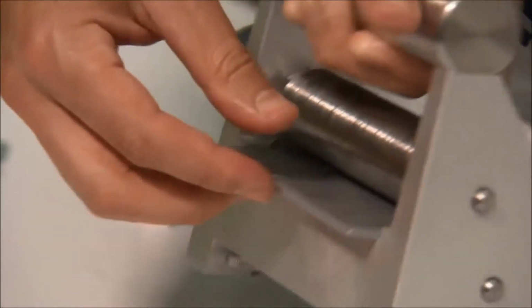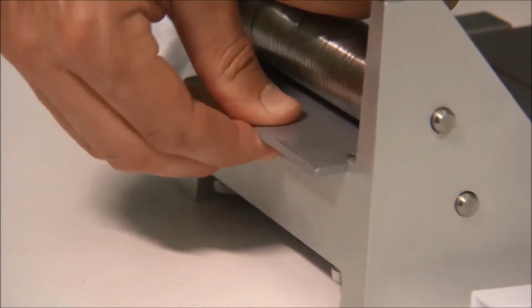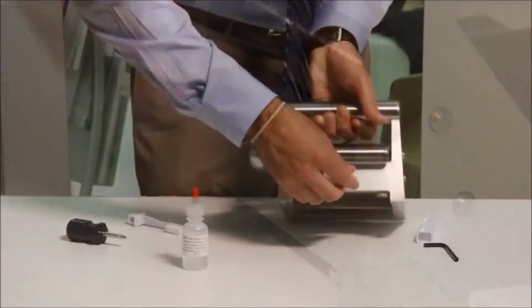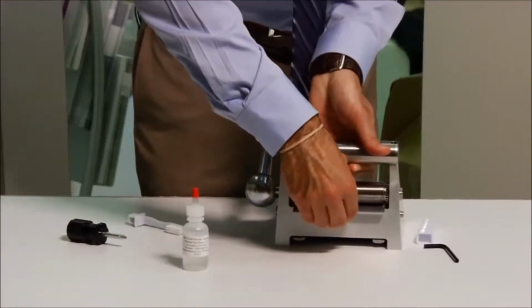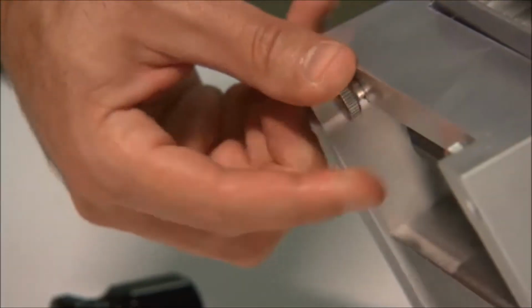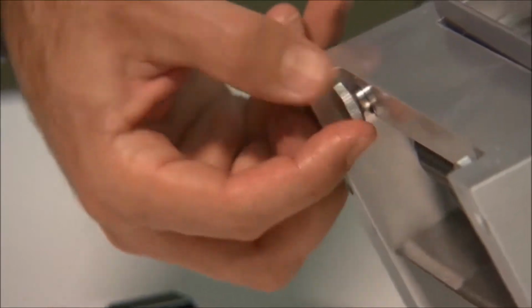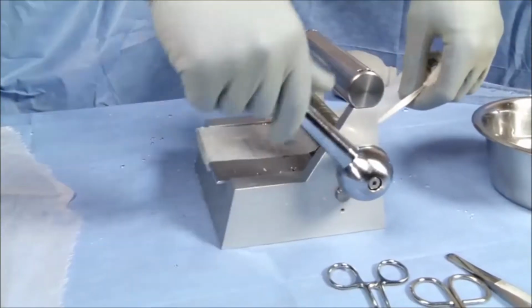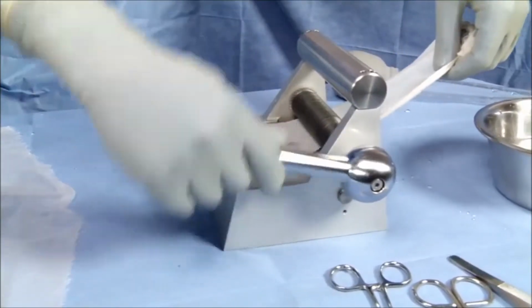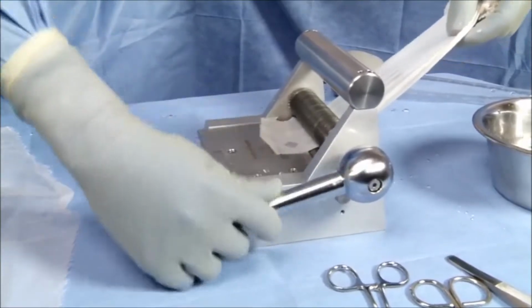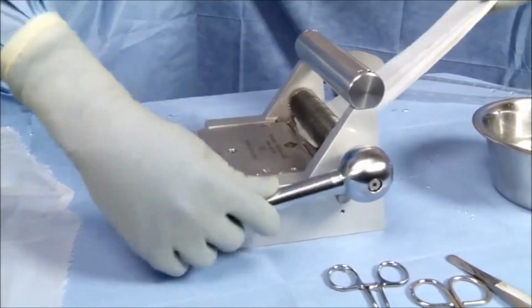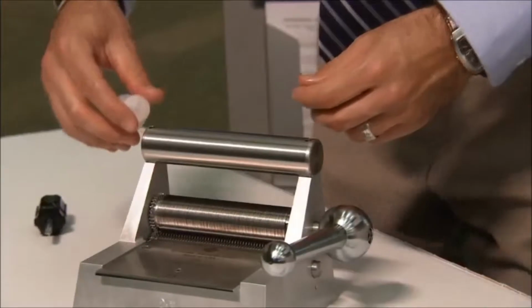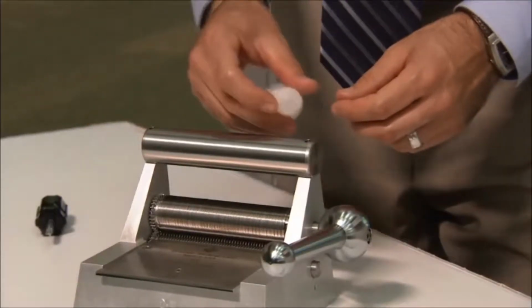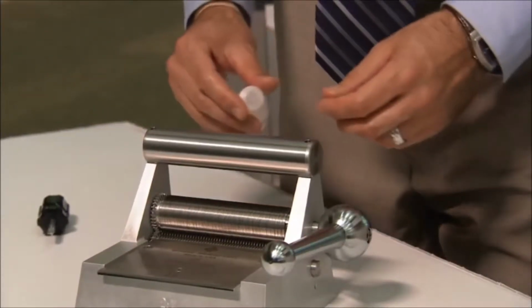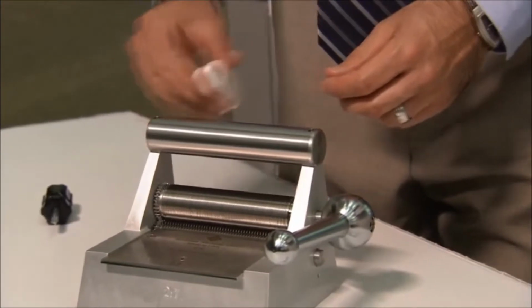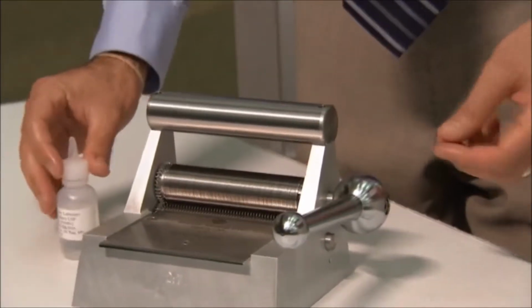To ensure the comb is fully secure, attempt to move the comb with your fingers. If the plate moves at all or makes a slight clicking sound, you should loosen the thumb screws and try again. If the comb remains loose or out of alignment for a grafting procedure, the skin graft could get caught in the mesher and might become damaged. The Brennen Skin Graft Mesher should be lubricated with 3 to 4 drops of mineral oil, placed in each of the 2 oil holes located at the top left and right of the handles.